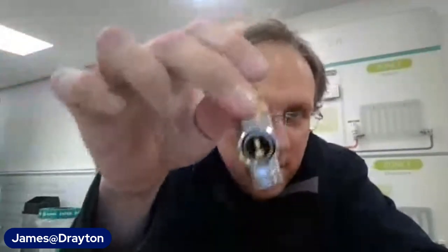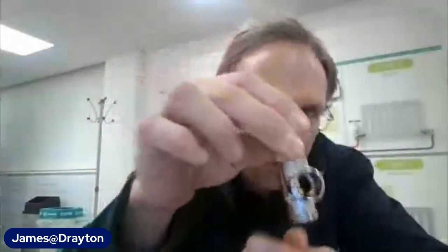Okay, so that's why we do it. And that's really talking in terms of the old-fashioned way of doing it, where we've got a lock shield valve at the other end, and we're adding resistance to the system by throttling down the aperture inside here, which is still a viable way of balancing, but it just means it's a little bit more fussy in so much as it's quite iterative, because you have to do each radiator at a time, and you're really having to measure the difference between the flow in and the flow out of the radiator.